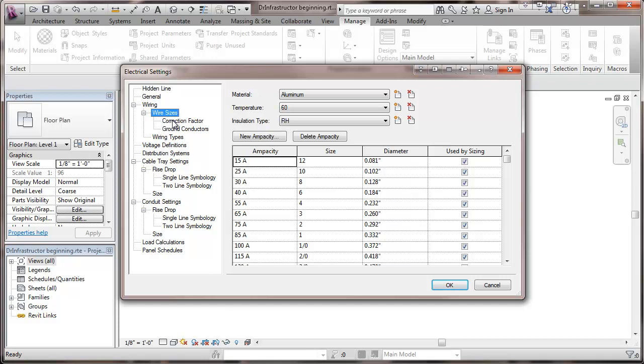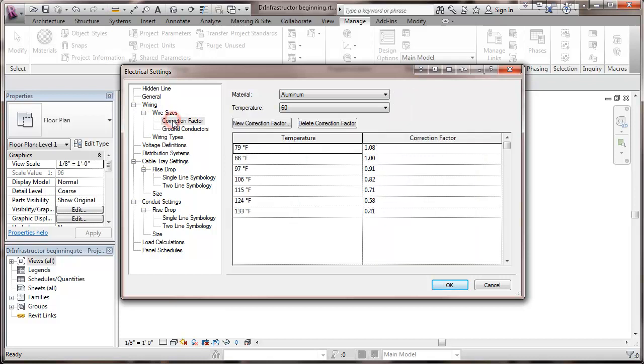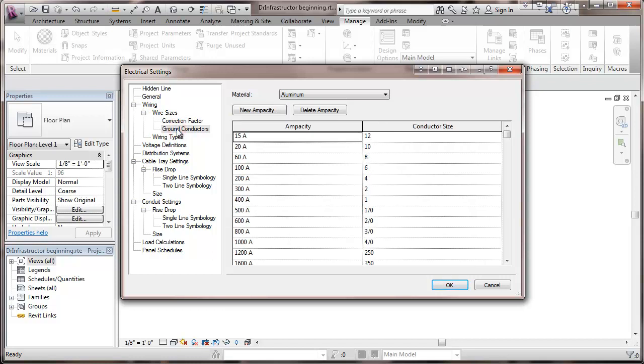There are also tables here for correction factors for higher ambient temperatures than the standard 86 degrees Fahrenheit. And there's a duplication here of sizing table that you see in the NEC. And this shows how ground conductors are calculated. It would be equipment grounding conductors.